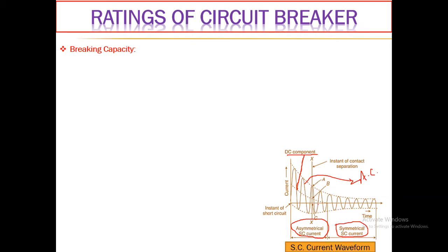The short circuit current waveform gives information related to different capacities when performing the short circuit test on a circuit breaker — symmetrical breaking capacity, making capacity, and so on. Breaking capacity determines the capacity of the circuit breaker to break the circuit when a fault takes place. It has two forms: asymmetrical breaking capacity and symmetrical breaking capacity.